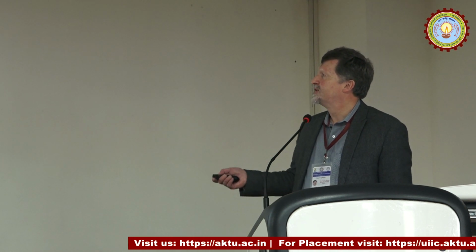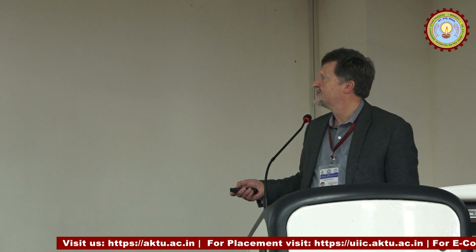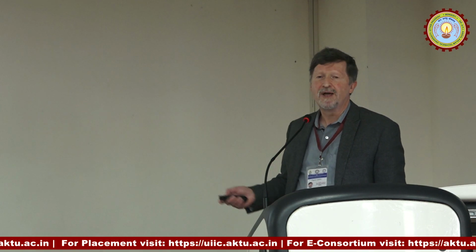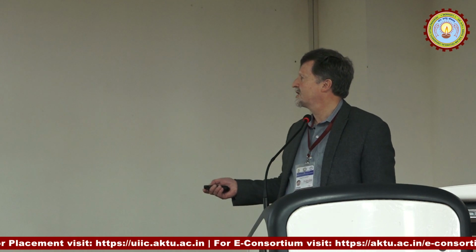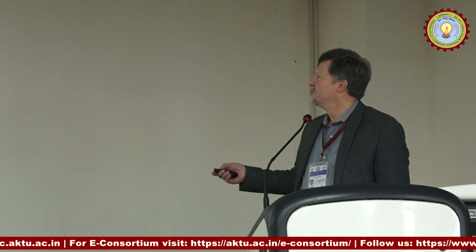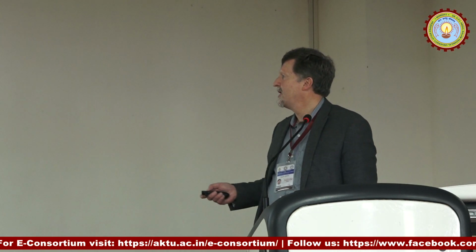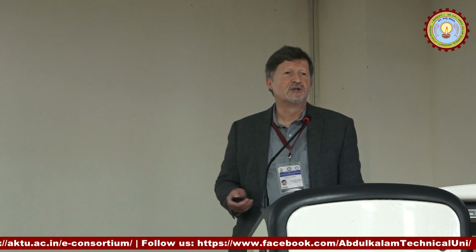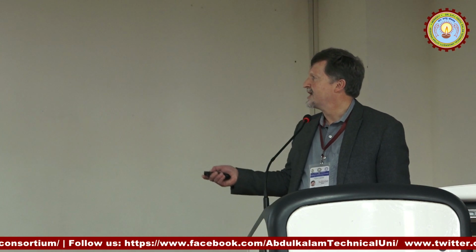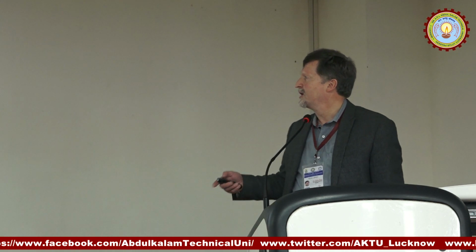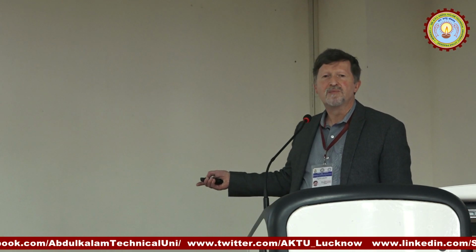And so the process is we start off with an initial object estimate. We do a forward projection of the current estimate into the time domain into which we're doing the reconstructions. We then look at the ratio of the measured data to what we've estimated, and then we use that ratio to back project into our original data set. And so we update this, and we can iterate this over a number of different iterations, so moving hopefully closer and closer to the measured data.